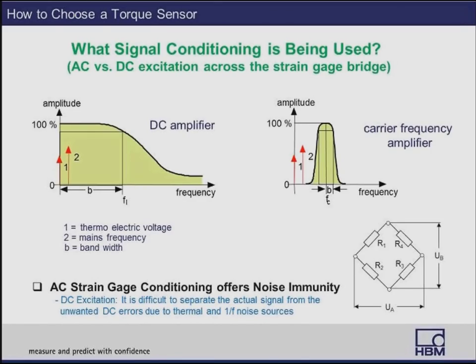What kind of signal conditioning is being used on the torque sensor — AC excitation across the Wheatstone bridge or DC excitation? At HBM, we recommend AC strain gauge conditioning. It is much more noise-immune than DC strain gauge conditioning. AC excitation minimizes errors that DC can cause, such as errors due to thermal or 1/f noise sources. It is always good to know what kind of strain gauge conditioning is used to excite the Wheatstone bridge.